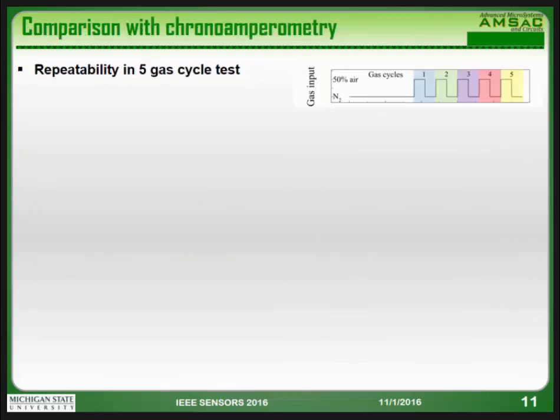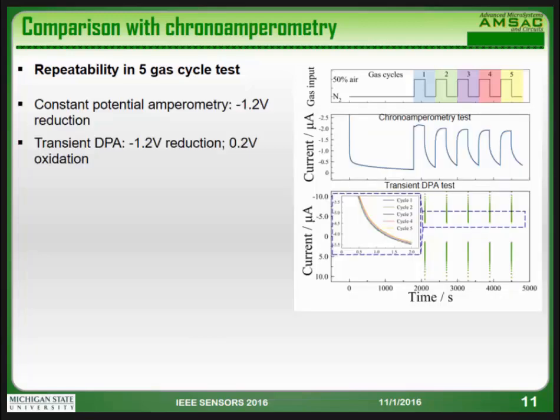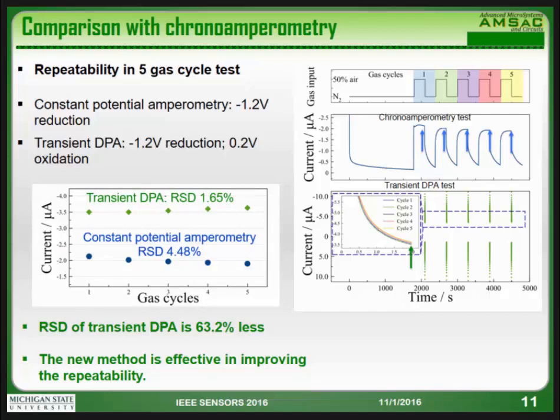Then we compare our method with the constant potential amperometry. The test is performed with 5 gas cycle tests. Here shows the gas input. We alternate the nitrogen and 50% air. And here shows the response of the constant potential amperometry and our method. The difference is that the transient method applies two potentials, and the constant potential amperometry only applies one potential. We also extracted the current signal, and we made a comparison here.